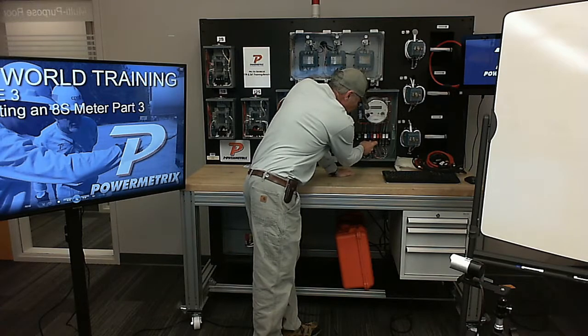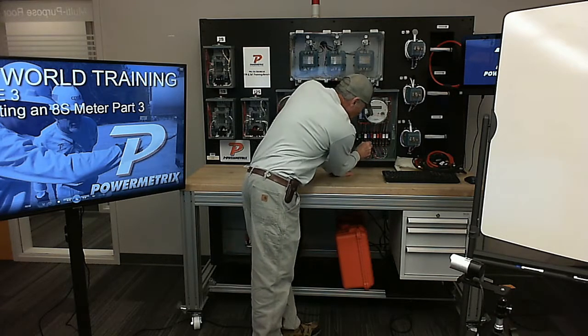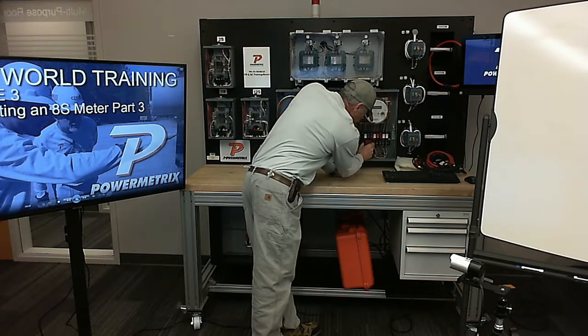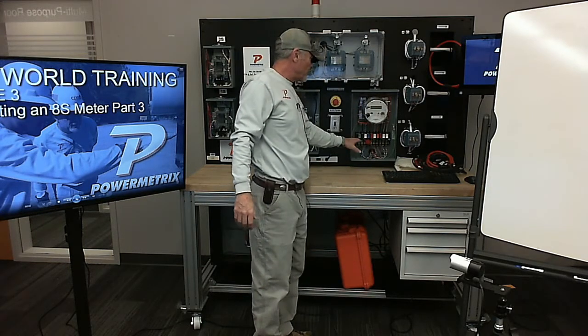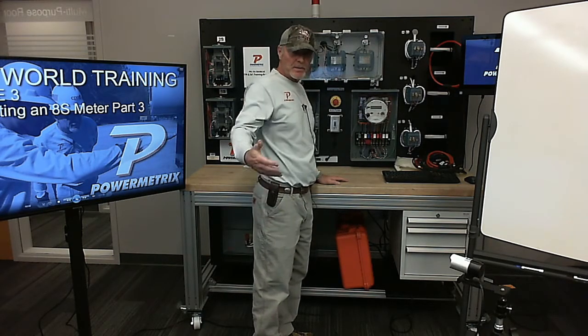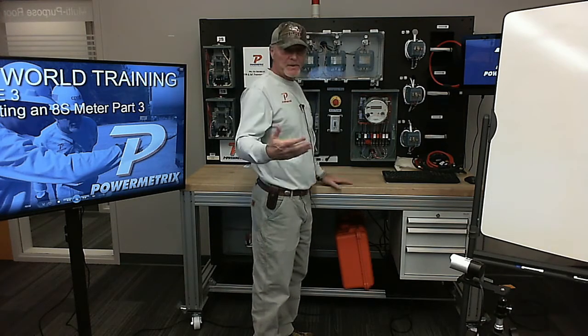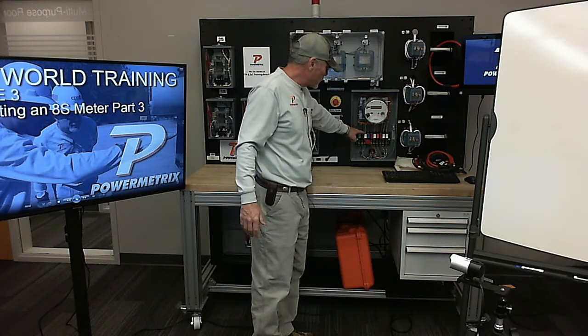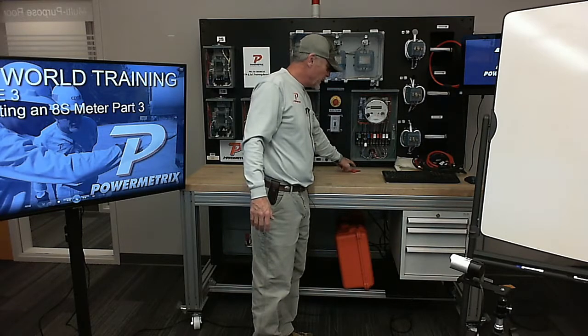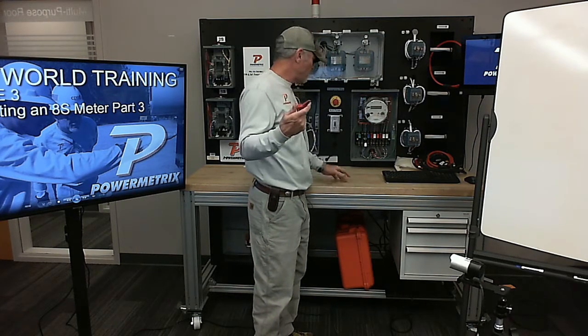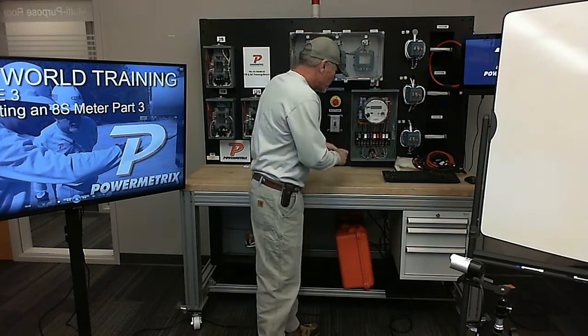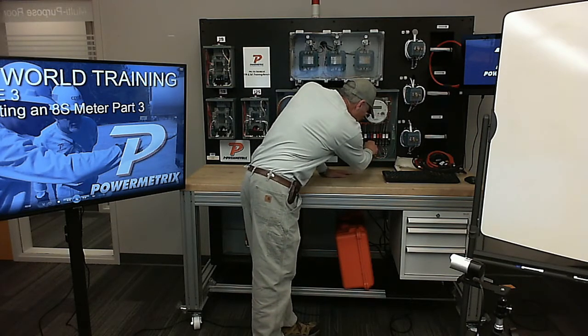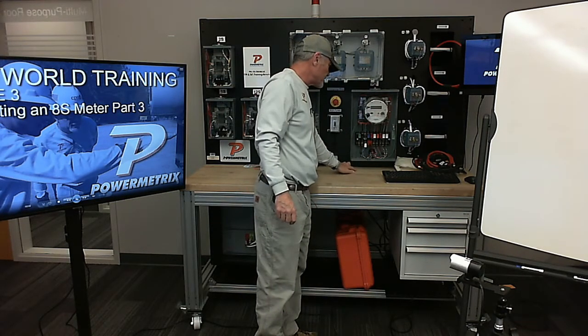If he turns the handle to the left and gets on this blade, what can happen is when you put your voltages on first, then put your duckbills in, opening that long stroke return blade wants to pull my voltage alligator clip off of there. So he always turns his to the right, and then when he opens it up, he doesn't have to worry about that.